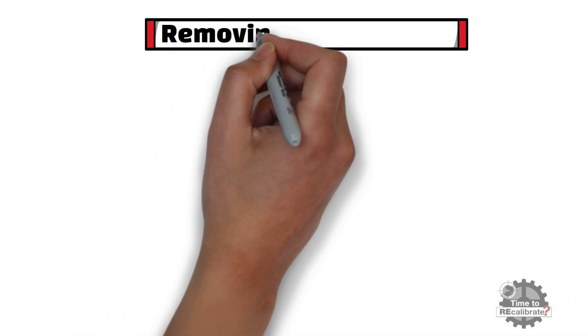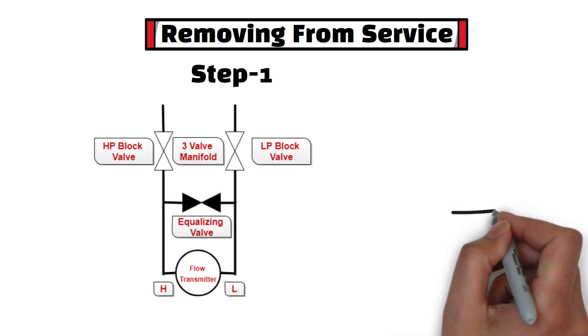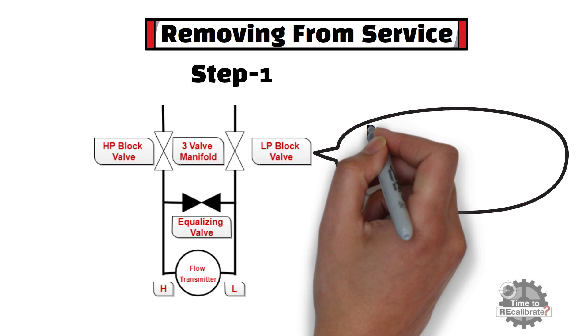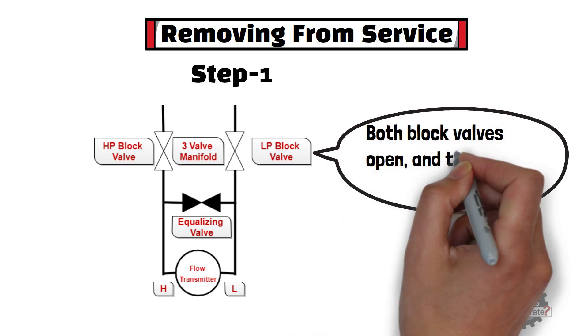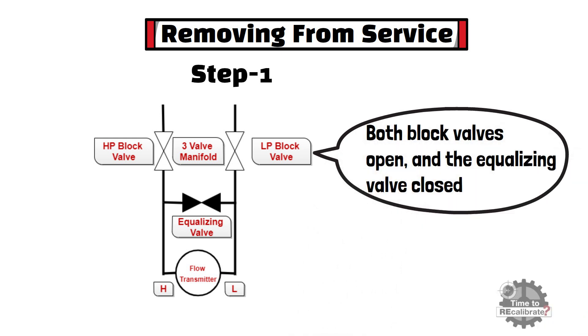In this section, I am going to show step-by-step procedure to remove transmitter from service. Step 1. As you can see, this is the standard orientation of the valves, with both block valves open and equalizing valve closed. In other words, this is condition of valves when transmitter is in service.